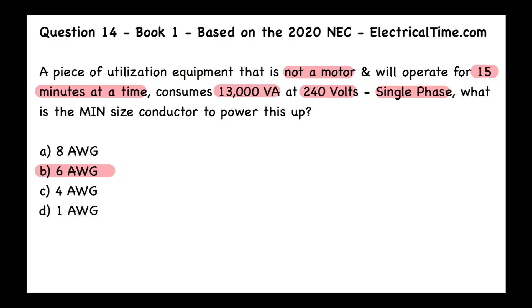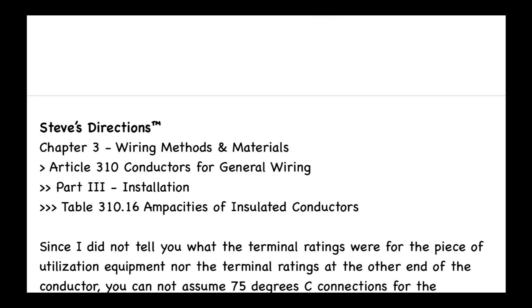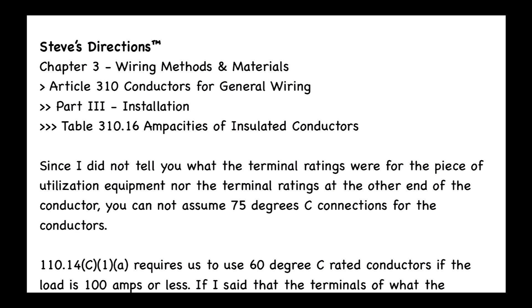A continuous load is one where the maximum ampacity will continue for three hours or more. Since this equipment only runs for 15 minutes, it does not meet that threshold, and we don't need to apply the continuous load multiplier.